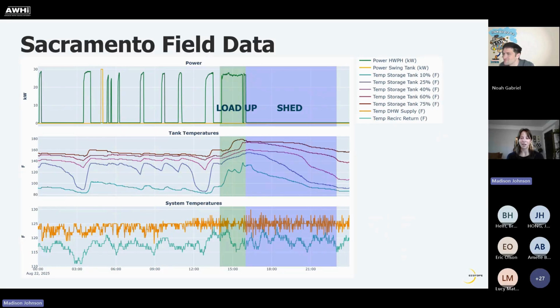Then looking at the middle plot, this is showing our storage tank temperatures at various heights in the tank. As we enter that green load up period, you can see all of our storage temperatures rise. The top of the tank gets up to about 180 degrees, so we're storing a lot of thermal energy in this tank. And then once we enter that shed period, we're kind of coasting through that stored energy. On this particular day, we still have quite a bit of stored energy left in the tank at the end of the shed period, so we're really not even reaching the full potential of what could be happening at this site.